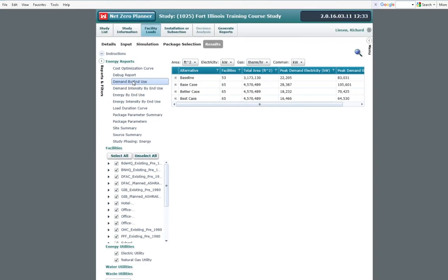So if you've got substation issues, in this case let's just pop this to megawatts. This gives you a really good idea of it. And so if you're looking at, let's just say, for example, for this area, you had 25 megawatts maximum as your available power, and after that, you'd have to invest in your electric infrastructure to give you more. And you can see right here, if you built those extra buildings, that you would exceed the capacity.